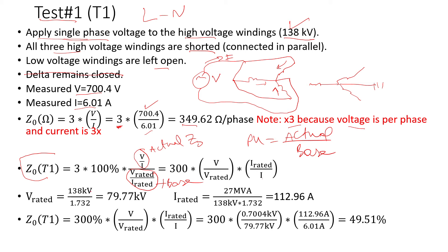The winding I'm applying voltage to is 138 kV, but I need the phase-to-neutral voltage, so I divide by √3, giving 79.77 kV as the rated phase voltage. The rated current for the high voltage winding is 27 MVA divided by (138 kV × √3), which equals 112.96 amps.